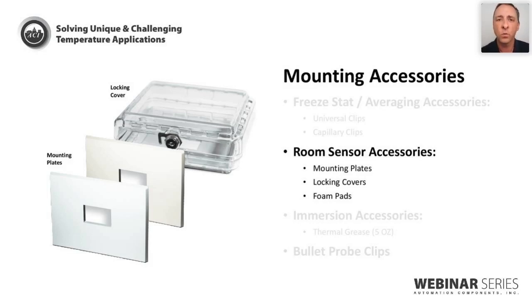Not shown here, but we do offer foam pads that can be affixed to the back of any room sensor housing to help insulate the sensor from any draft that might come from the backside, through the wall. So we recommend the foam pads if a sensor has to be placed on an exterior wall, and we can either provide the pads separately. They just have a simple adhesive back that can be applied to the back of the wall sensor, or we can install the pads onto the housings here at the factory.